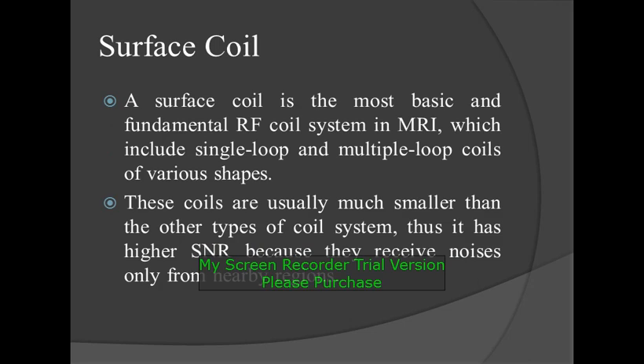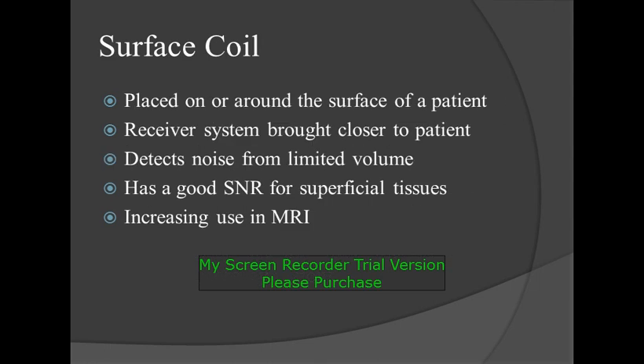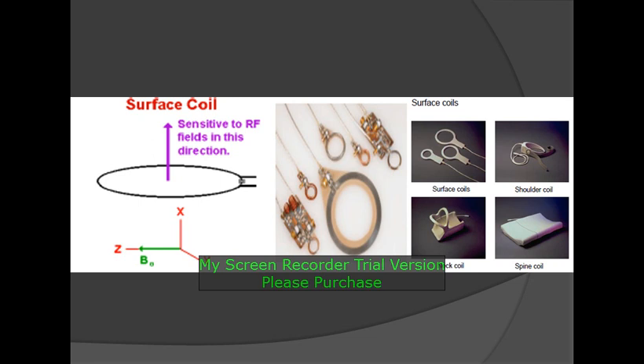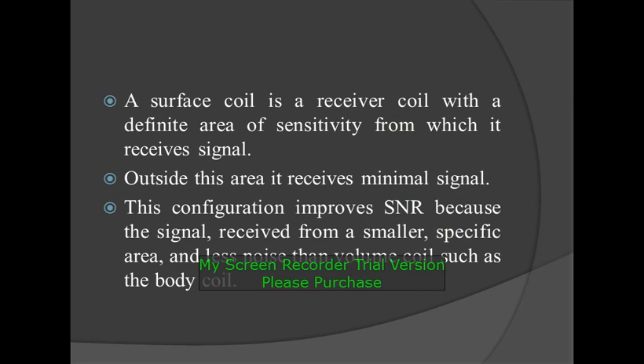Surface coil: a surface coil is the most basic RF coil system in MRI, which includes single-loop and multiple-loop coils of various shapes. These coils are usually much smaller than other types of coil systems, thus they have higher SNR because they receive noise only from nearby regions. Surface coils are placed on or around the surface of a patient, bringing the receiver system closer to the patient. They detect noise from a limited volume and have good SNR for superficial tissues. A surface coil is a receiver coil with a definite area of sensitivity, and outside that area it receives minimal signal. This configuration provides better SNR because the signal is received from a smaller specific area with less noise than volume coils such as the body coil.